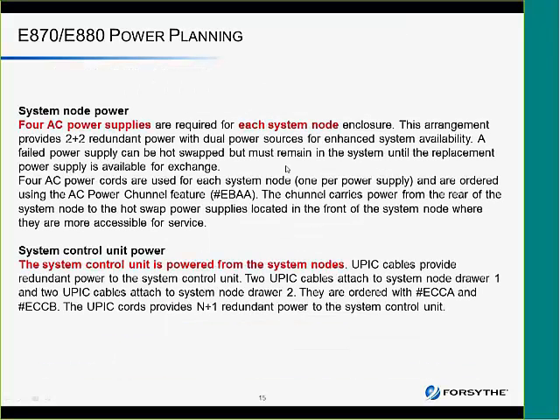So for power planning for an 870 and 880, it requires 4 AC power supplies for each system node enclosure, and that's a 2+2 redundant. And the reason for that, as I said before, is because the E870 is around 19 amps or 4.2 kVA, and clearly, since each pair of plugs has a 20 amp circuit, and has a 10 amp per plug, if we're going to be pulling 19 amps, then we need to split that across not just 2 plugs, but across 2 of the circuits in the PDU. So you cannot plug a pair of AC power supplies into the same pair of plugs on the PDU. They have to be on different spots on the PDU.